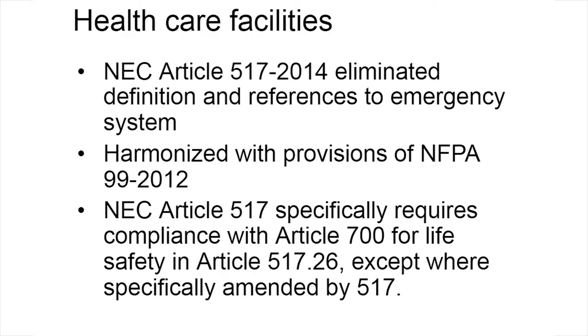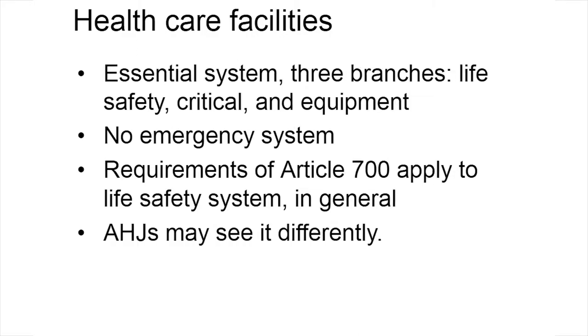There's been a bit of an ongoing battle between the writers of NFPA 99 and the writers of Article 700 in the NEC for a couple of cycles now. The NEC describes more restrictive requirements, and NFPA 99 says they don't apply to hospitals. This one, I think the fire protection will probably apply.